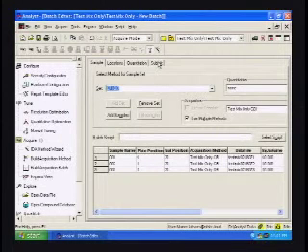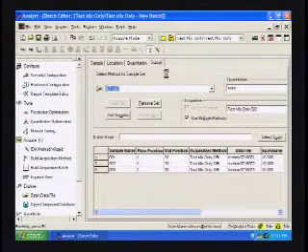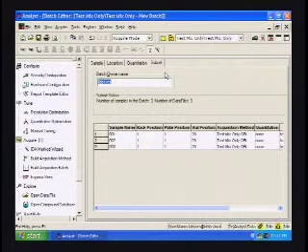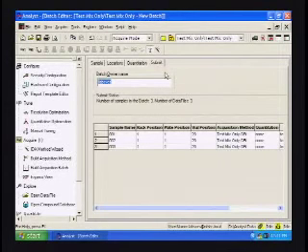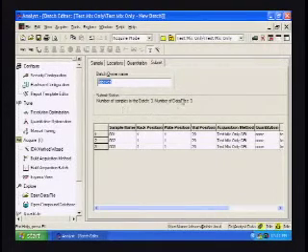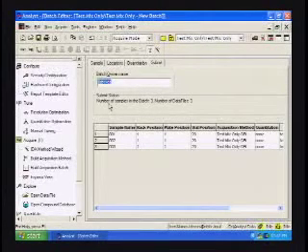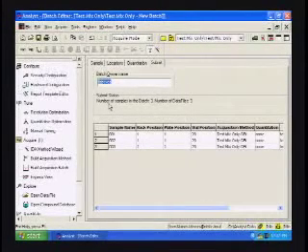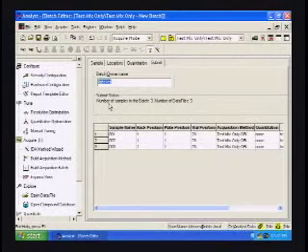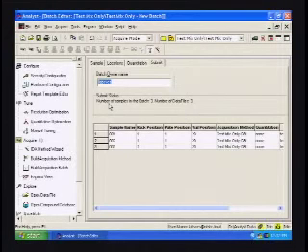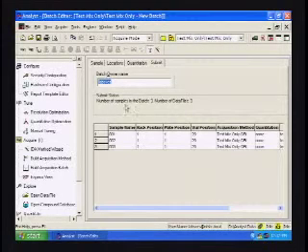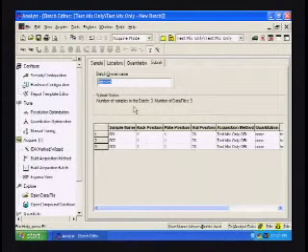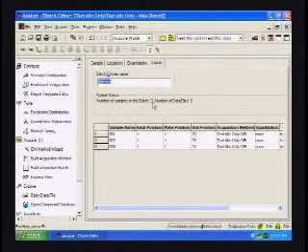The next thing we want to do is we want to submit the samples to the instrument. This particular space right here is really useful for determining if you've made any errors in setup of the batch acquisition. There is no indication of any errors here. It said that there's three samples in the batch and there's three data files. If we put them all in one data file, it would have told us that here.